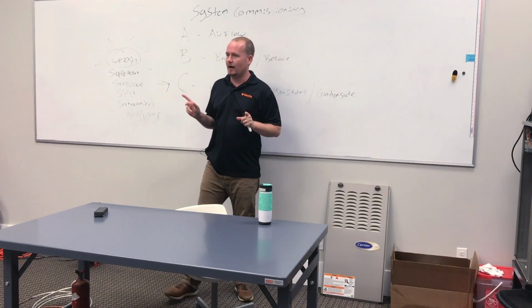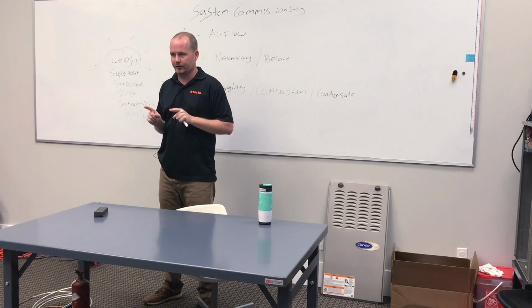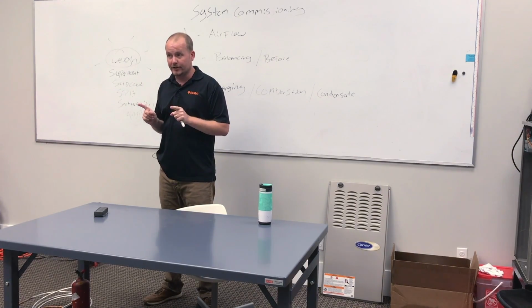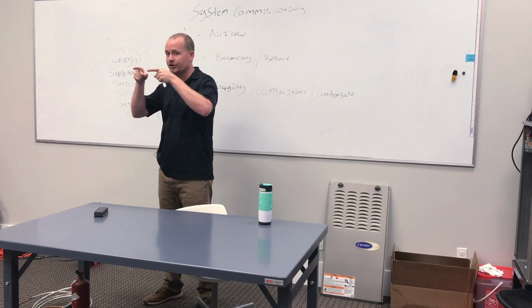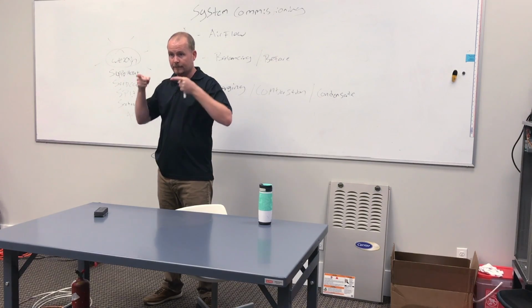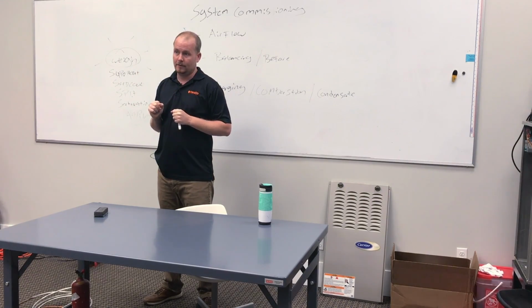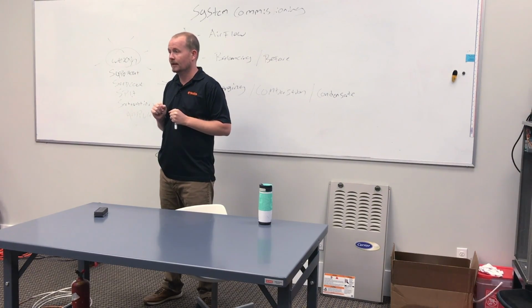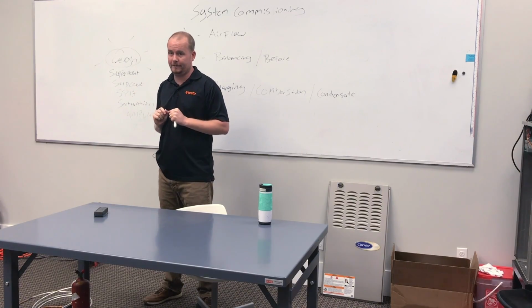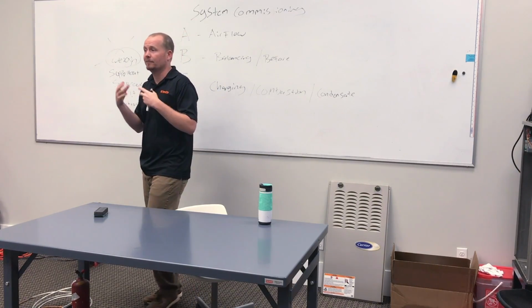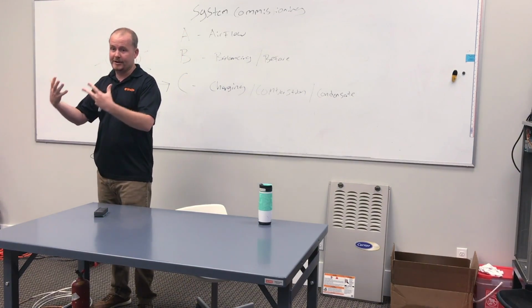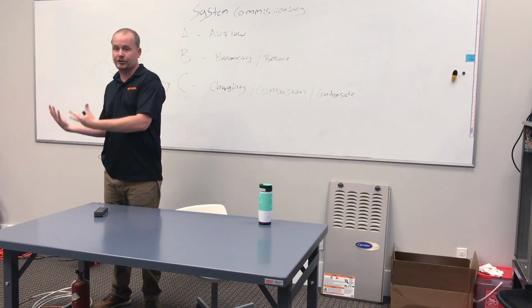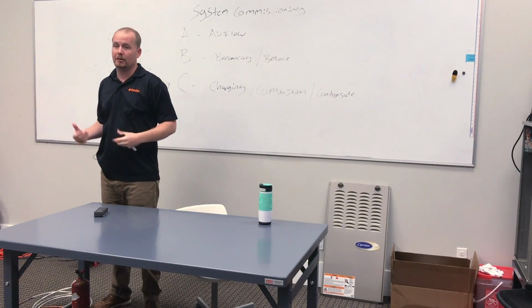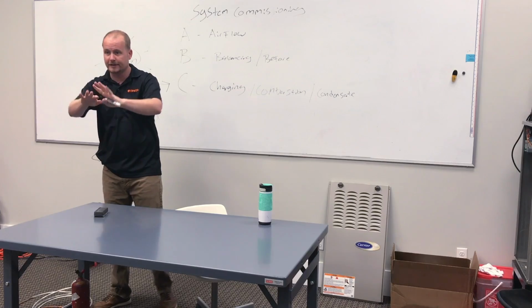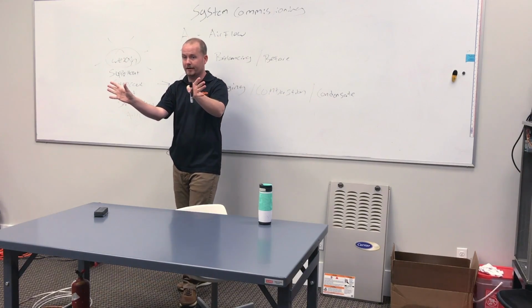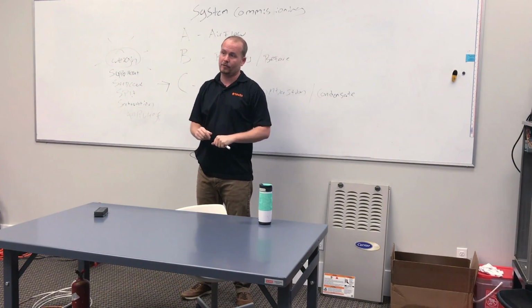But I know right now, if I were to go watch most of you, you're not checking voltage. But checking voltage is actually more valuable, because when you check the voltage while it's running, going into that contactor, what is that telling you? It's telling you the voltage under load. So it's going to tell you if you have problems with your circuit. If you have issues with connections, you're going to have voltage drops. It's going to tell you, am I applying the proper voltage to that unit? What's cool is that the unit tells you what the acceptable voltage range is right on it. So you can note, am I giving it the right voltage?